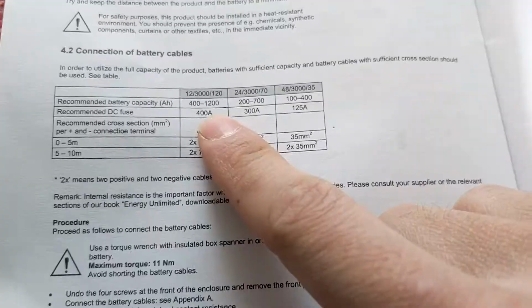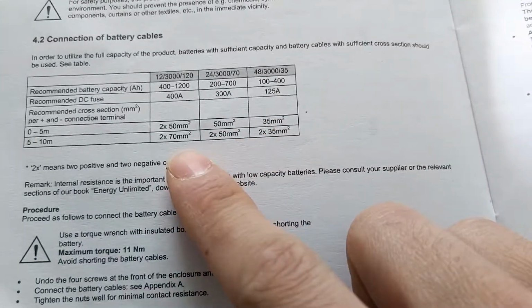Once you've figured out what size wire you need, size your fuses and circuit breakers. The first thing I'd recommend is looking at the inverter you've chosen and figuring out what they recommend. A lot of inverters recommend both wire sizing and fuses. Mine recommends a 300 amp fuse with 50 millimeter squared wire, which is 1-gauge wire. I went a bit up to 1/0 gauge, but that can't hurt since it just minimizes voltage drops.